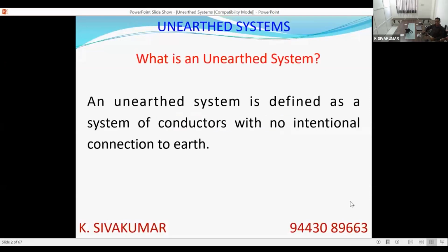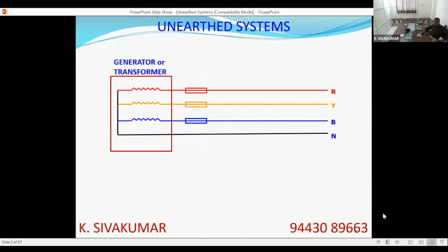So, starting again. This unearthed system is a system in which there is no intentional connection to earth. As you are aware, in an earthed system, we intentionally connect the neutral to earth. In an unearthed system, it is not done. The network will look something like this: the source may be a generator or a transformer, 3-phase 3-wire or 3-phase 4-wire, the distributed neutral may or may not be there, but the neutral is not connected to earth either directly or through any impedance. This will be the typical arrangement of the unearthed network.